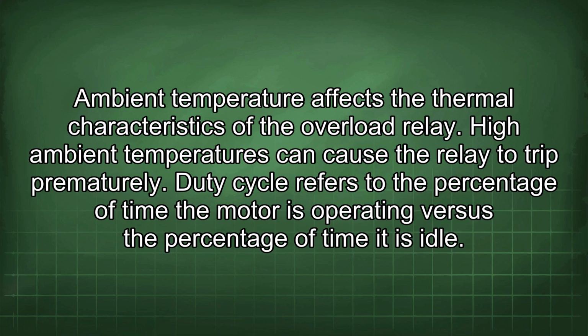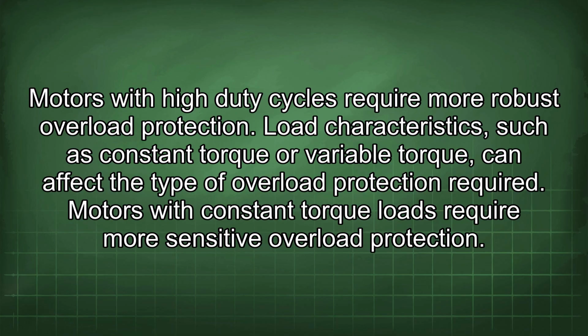Duty cycle refers to the percentage of time the motor is operating versus the percentage of time it is idle. Motors with high duty cycles require more robust overload protection. Load characteristics, such as constant torque or variable torque, can affect the type of overload protection required. Motors with constant torque loads require more sensitive overload protection.